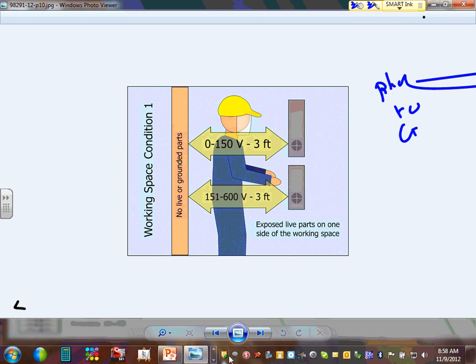Condition 1 is a sheetrock wall. Here's condition 1 right here. Sheetrock wall. I'm a panel in front of the sheetrock wall. Ungrounded object, 3 feet. If your system is between these two values, it's also 3 feet. Any question, guys, about clearances in the front of panels?